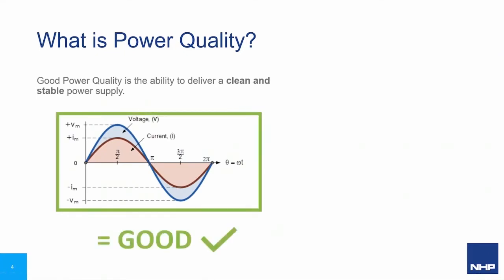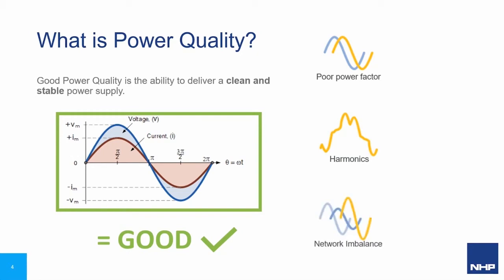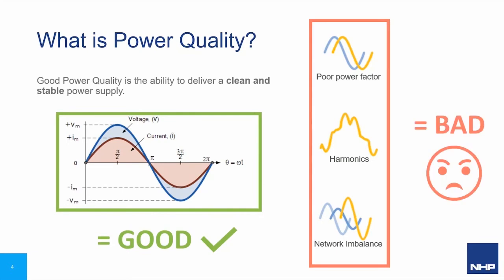There are three main power quality issues commonly faced. First is power factor. A poor power factor results in a phase angle difference between the current and voltage waveforms of an AC system. Second is harmonics, which are multiples of the fundamental frequency of 50 Hz impacting the supply, resulting in heavily distorted waveforms. Finally, we have network imbalance, which is differing line voltages across phases caused by unbalanced loads and single phase and phase-to-phase connections.